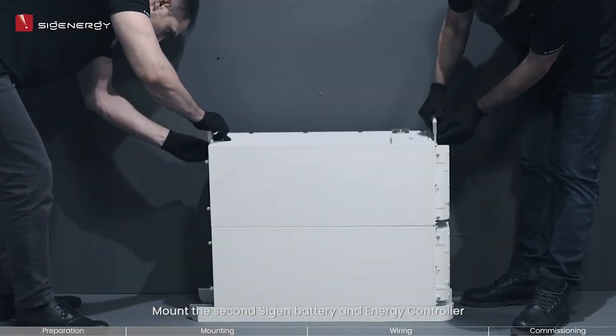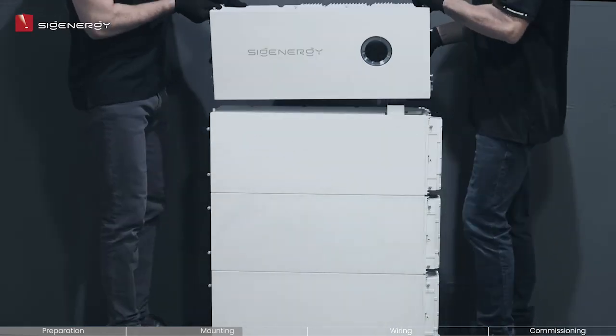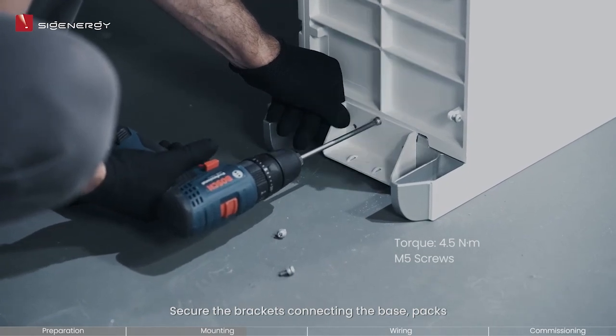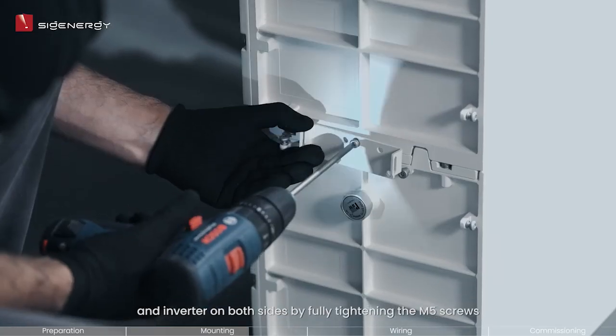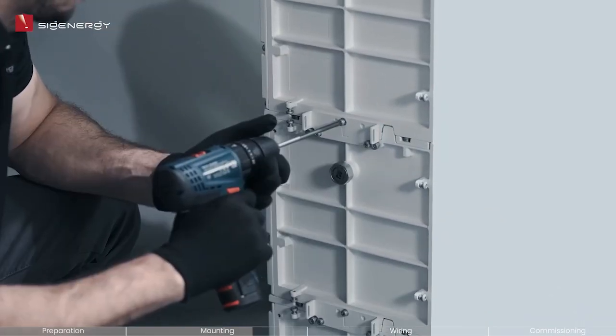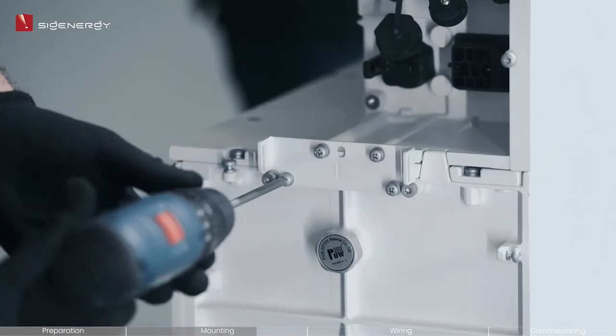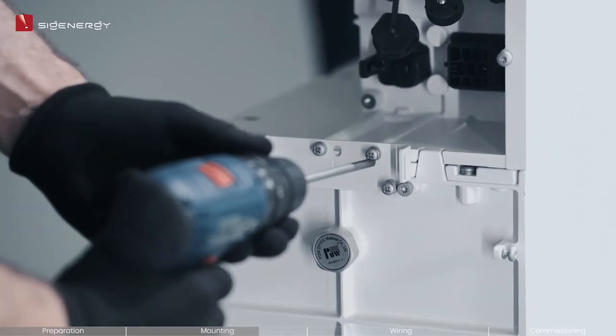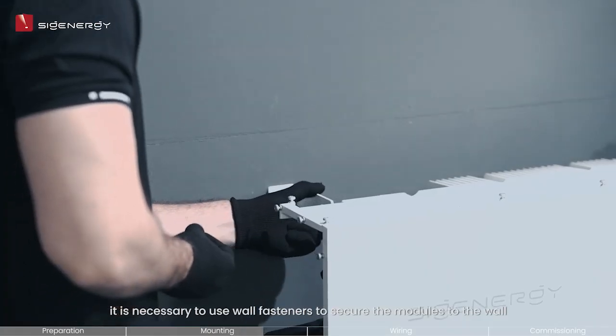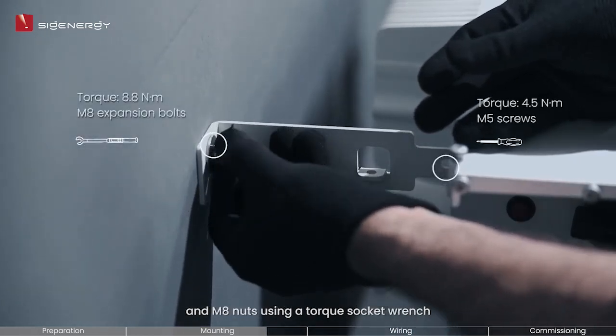Mount the second Sigen battery and energy controller using the same procedure as before, ensuring proper alignment of the quick connectors. Secure the brackets connecting the base, packs, and inverter on both sides by fully tightening the M5 screws. For optimal stability, it is necessary to use wall fasteners to secure the modules to the wall. Make sure to tighten the provided M5 screws and M8 nuts using a torque socket wrench.